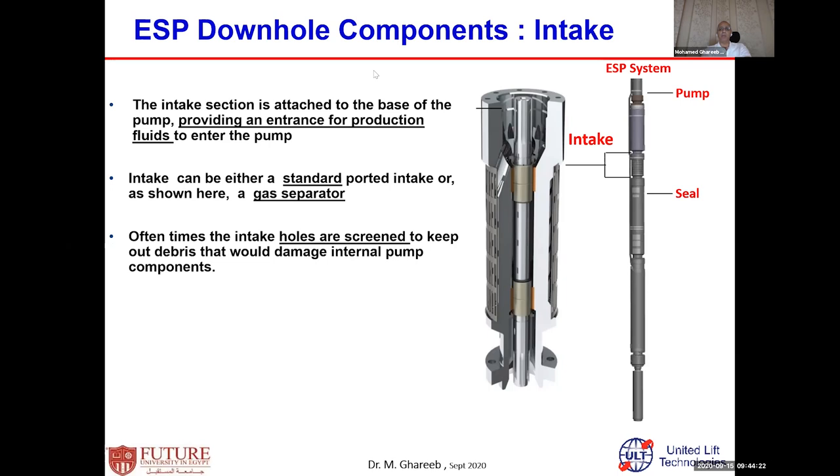Another piece is called the pump intake. From the word intake, it is the part that takes the fluid and brings it into the pump. It takes the fluid from the bottom of the well and allows this fluid to pass to the bowl. The intake is a section, and the top of the intake is attached to the base of the bowl, usually providing entrance for the fluid to the bowl. The main function of this standard intake is to allow fluid to enter the bowl. It connects to the bowl from the bottom, and then the bowl connects to the top.